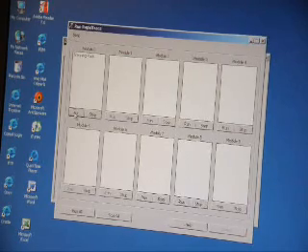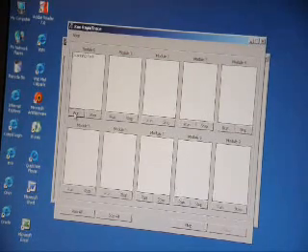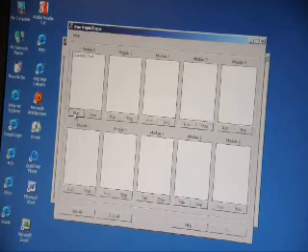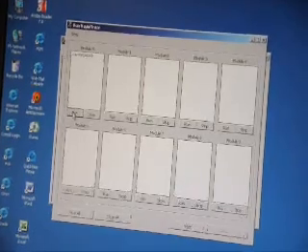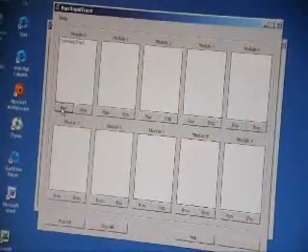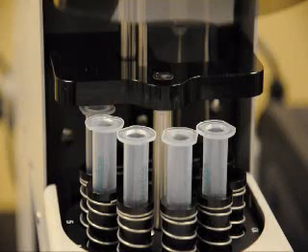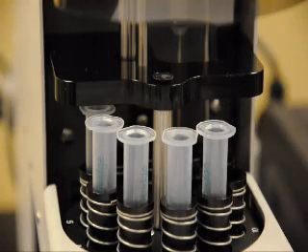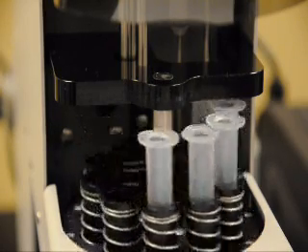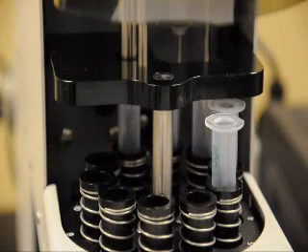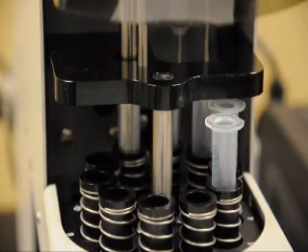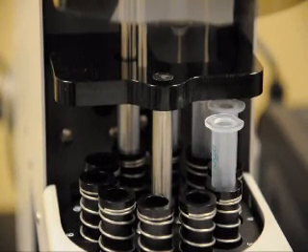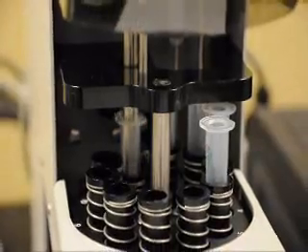As the method runs, this screen will have a dialogue telling me what steps are happening, what samples are running, and the approximate run time, so I know when my samples will be finished. As we start the run, once the shuttle has scanned the rack, you'll see the turret turn to position to the first SPE column, which is column number one. The column plunger goes down inside the column and then is going to push the column into the waste station, into the location that we've specified as organic waste.